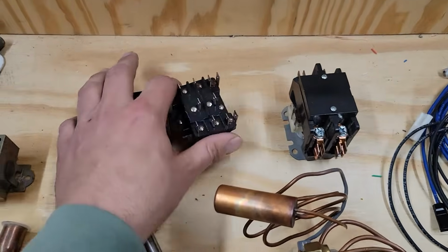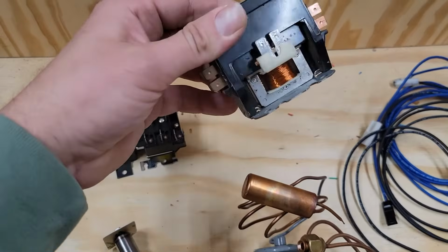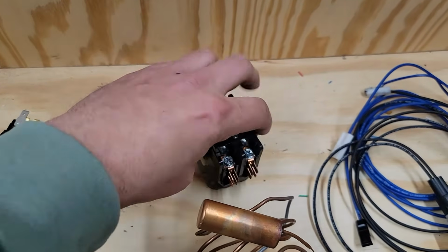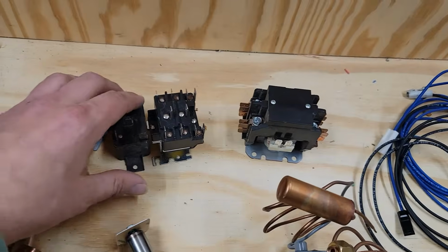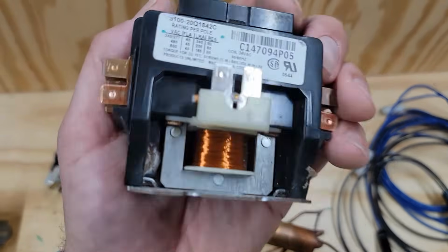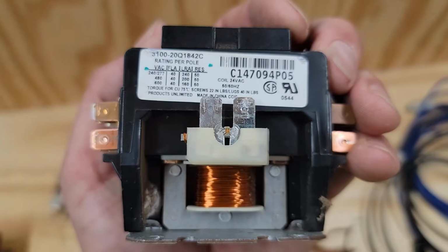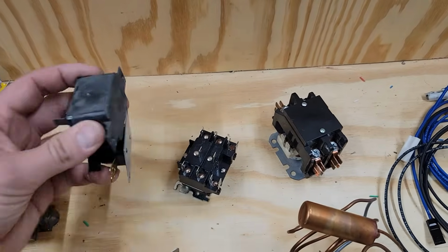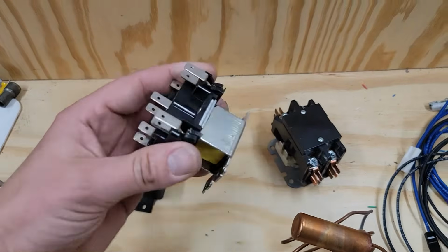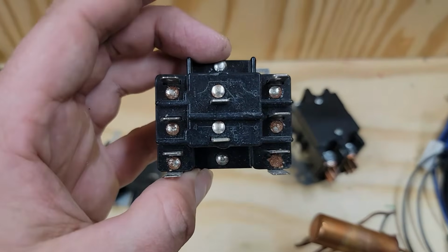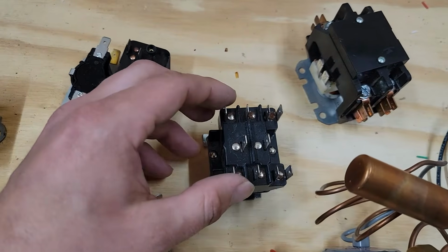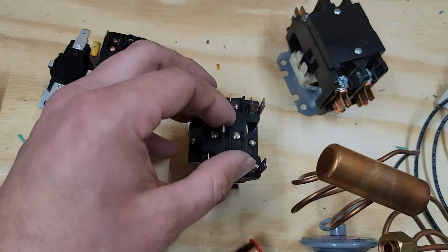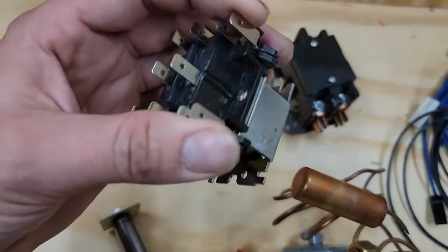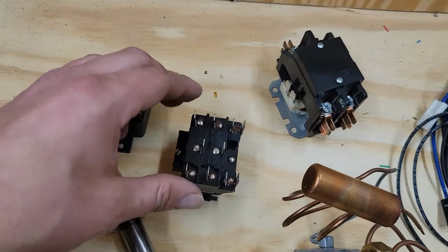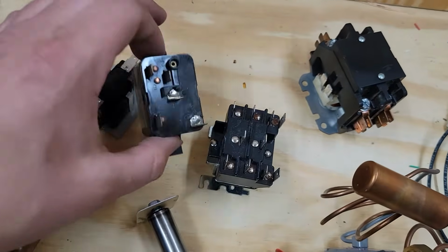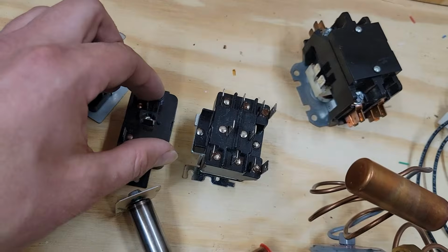And the difference between these three relays right here and this contactor is, this contactor is used to control bigger loads that have more current, and typically you'll see it control more than 20, 30 amps, sometimes 40, 50 amps, and then this right here is only rated for probably 20 amps or so. This right here is a 9340 relay, and you've got a set of normally open and normally closed contacts, and then you've got your coil right here. This is where your low voltage goes, and this is where your high voltage would go. Same thing for this. You've got a coil, and then you've got contacts.